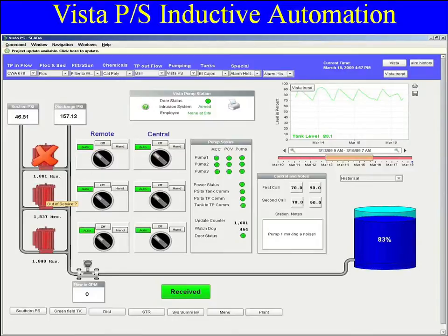You can see they have a couple of features that are really nice. The trending object is superior to Wonderware. If I pull up a one-month trend on just one signal and time it, it takes 42 seconds to pull that data off the PC. When I'm using the Inductive Automation product and I ask for a one-month trend, it's instantaneous — as soon as I click the mouse, the trend is painted in.